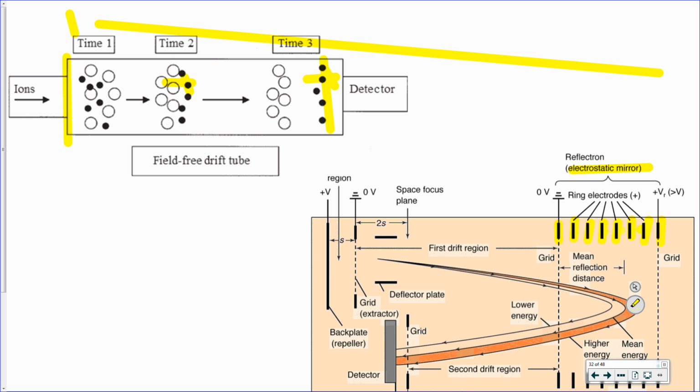They're dividing this voltage up in a series of steps, typically 10 steps, slowing the ions down until finally the opposing voltage stops them, and then it makes them run back the opposite direction. You put it at a slight offset angle so they come in, slow down, stop, then accelerate back out, and you can make them run down the entire length of the tube again, effectively doubling your path length. So you increase your resolution.